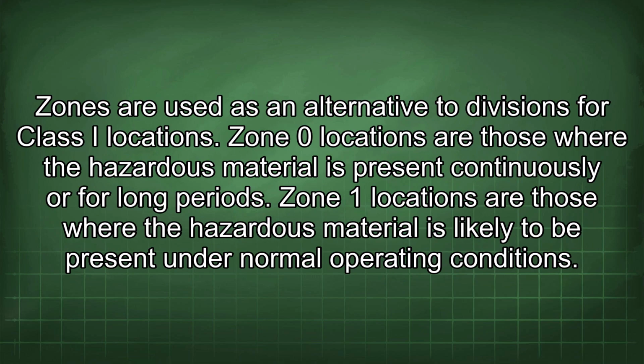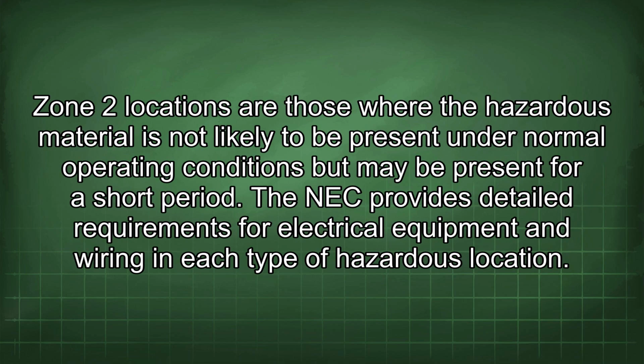Zones are used as an alternative to divisions for Class I locations. Zone 0 locations are those where the hazardous material is present continuously or for long periods. Zone 1 locations are those where the hazardous material is likely to be present under normal operating conditions. Zone 2 locations are those where the hazardous material is not likely to be present under normal operating conditions but may be present for a short period.